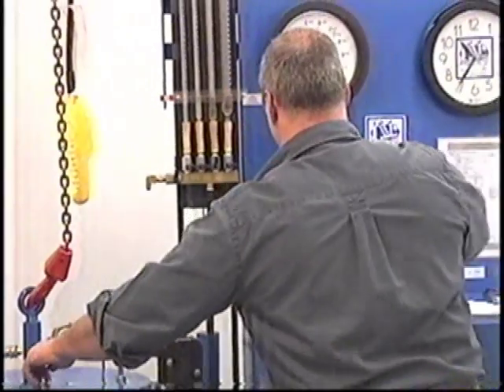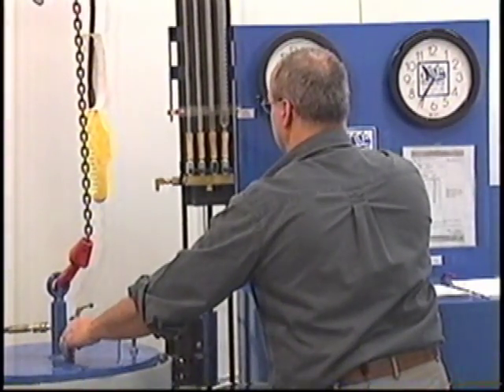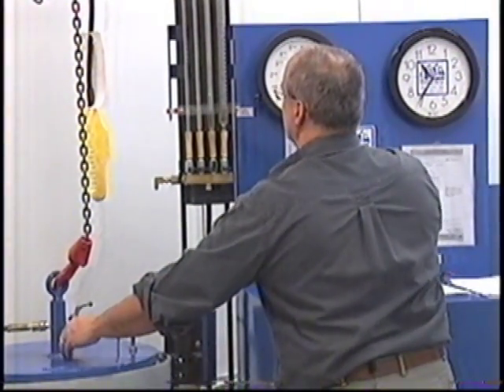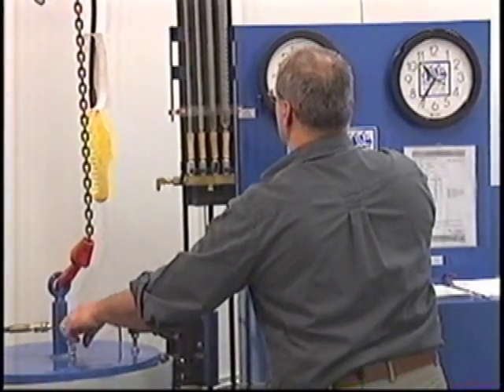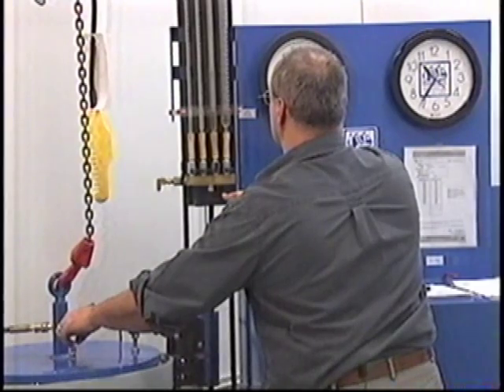The operation is very similar to your calibrated cylinder. Again we are going to make sure that all the air is out of the water jacket. We pick out the burette tube that we are going to use and bring that water level down to zero.